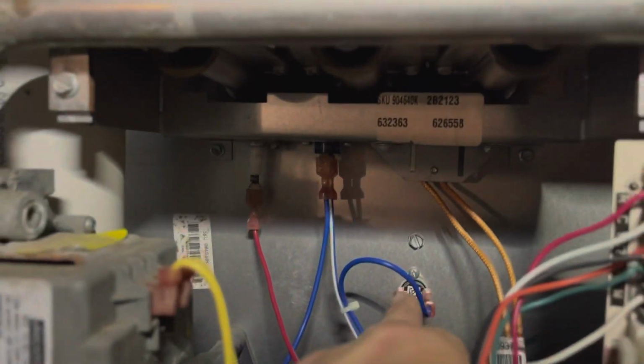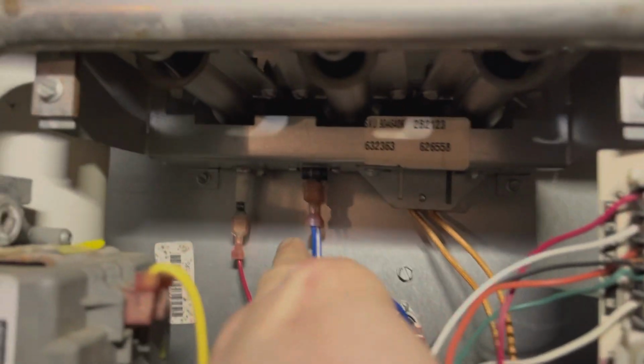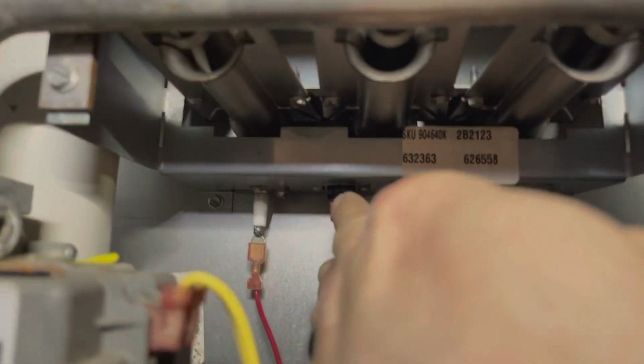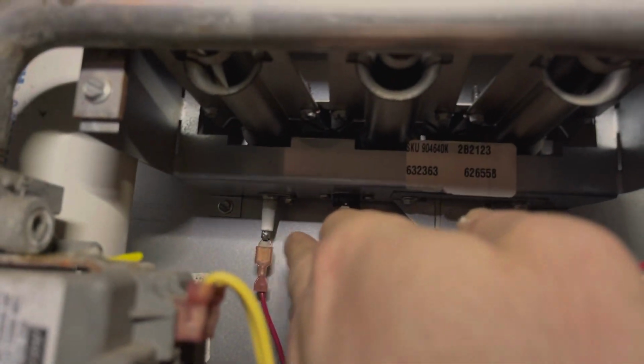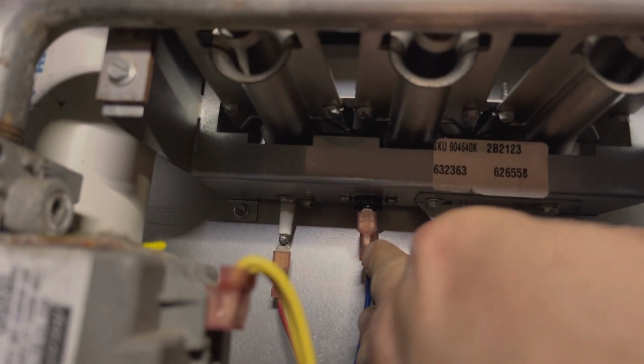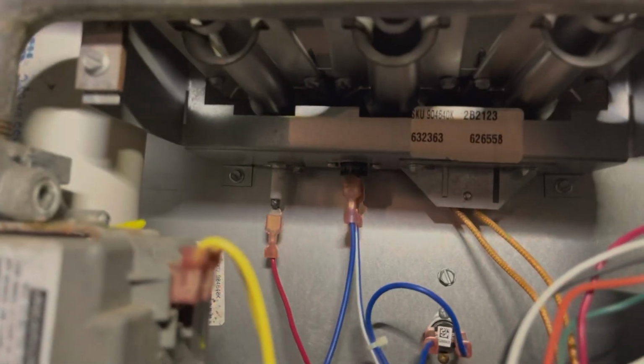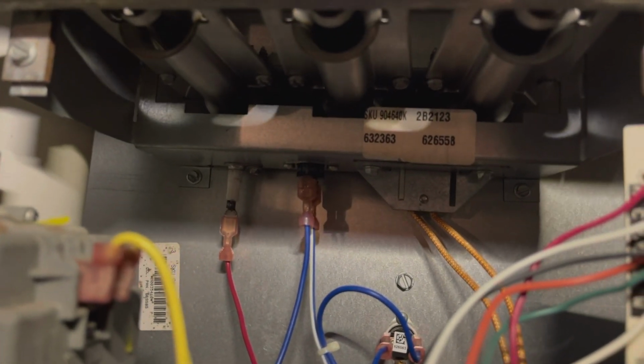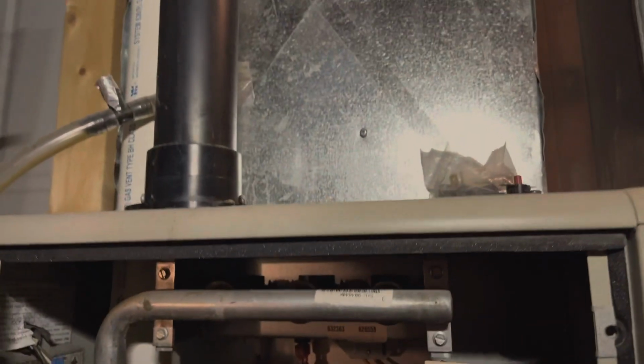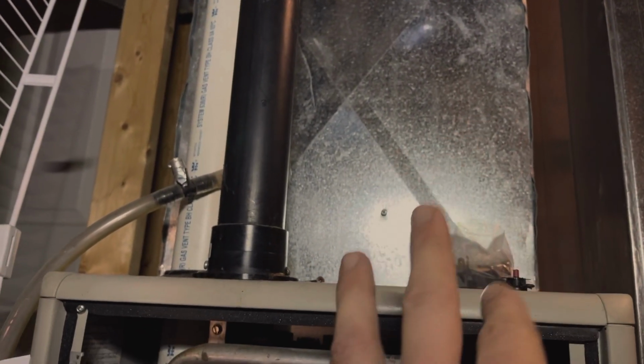But this is going to sense for the blower motor to turn on and off. So if you're hearing issues with your blower motor on and off, it could be these, it could be your solenoid and whatnot. But so then you're going to see your flame light up, it's going to sense it, the blower motor should be working. So it could trip off if you have a bad furnace filter, possibly, if it's really having a bad issue. Big issue you could have is above there is your heat exchanger. And if the heat exchanger is clogged up, it can cause this to trip.